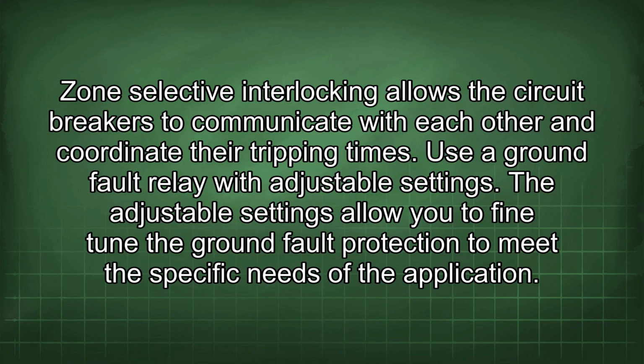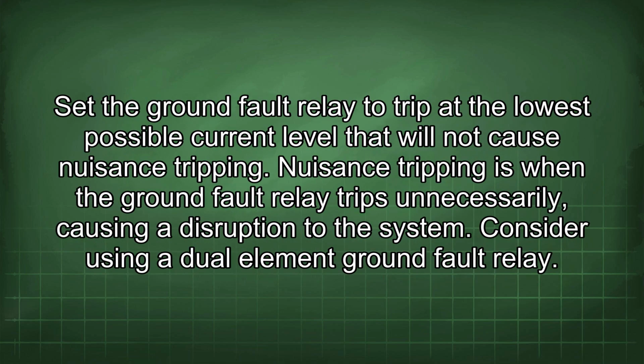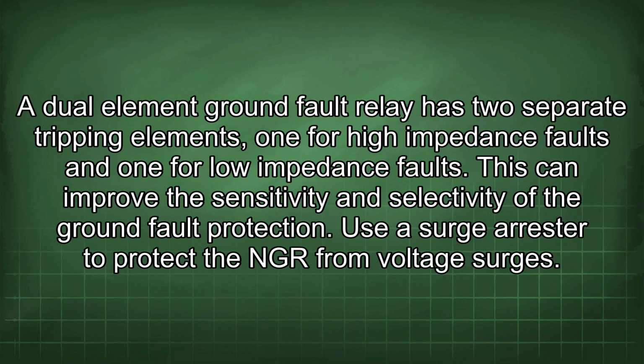Use a ground fault relay with adjustable settings. The adjustable settings allow you to fine-tune the ground fault protection to meet the specific needs of the application. Set the ground fault relay to trip at the lowest possible current level that will not cause nuisance tripping. Nuisance tripping is when the ground fault relay trips unnecessarily, causing a disruption to the system. Consider using a dual-element ground fault relay. A dual-element ground fault relay has two separate tripping elements, one for high-impedance faults and one for low-impedance faults. This can improve the sensitivity and selectivity of the ground fault protection.